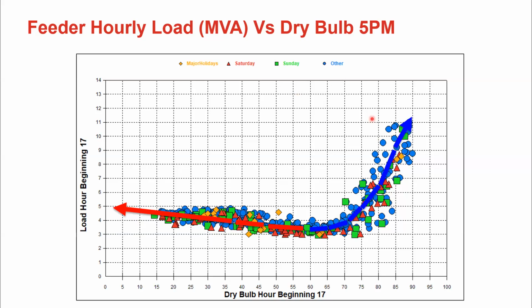We're looking at different period lags to capture the heat buildup effect, because it takes a while for the building shell to actually heat up and feel what's coming in from outside. Additionally, we'll look at offsets. This particular feeder is residential dominant, so you don't see much difference in slope between weekdays and weekends, but we're able to capture those offsets for more non-residential dominant circuits. We'll also look at impacts of wind and clouds, enabling us to be very accurate at the feeder level.